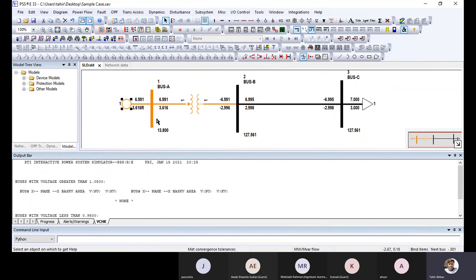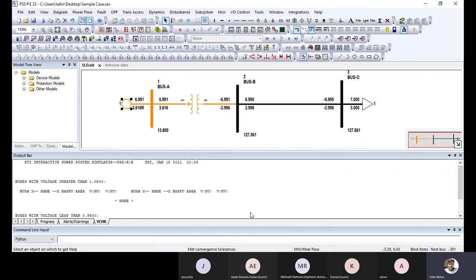Okay. So PGen is basically the maximum megawatt, the net megawatt that is coming at this bus. You can see at this bus 6.991 megawatt is coming. I mean, this is the megawatt entering at the POI, the point of interconnection. And sometimes some larger plants, like a coal plant, have their own colonies and different facilities and departments inside the plant, so they have auxiliary load also. So what they do is place the auxiliary load here, like 2 megawatt. Okay, now I have added that auxiliary load here.